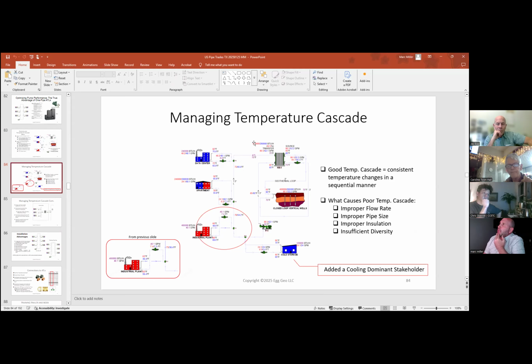And if we look at our BTUs that are being discharged now, it's 260, right? In the last slide, what were we? We were 140. So we went up by 120,000 BTUs, which is this stakeholder. Well, it's being rejected by the heat exchanger because there's no other heating dominant in this particular scenario at this snapshot in time. There's nobody else to absorb that heat. Because remember, this guy here is absorbing the 400,000 BTUs from this guy here. So we're left with nothing but to discharge that heat through that heat exchanger. Now, in theory, the apartment building and the data center ultimately are also producing domestic hot water. So in theory, the apartment building and the data center would be consuming some of those BTUs, okay? But it's just not shown in this simplified representation of a thermal energy loop. So good cascade, good temperature cascade equals a good temperature change in a sequential manner, which we've shown here in this thermal energy network.